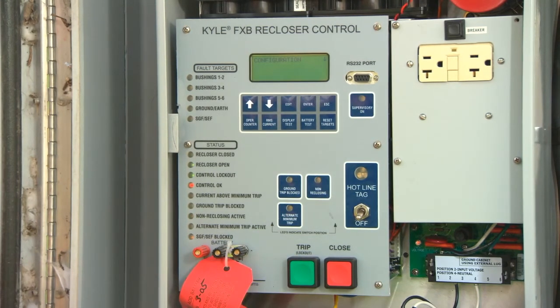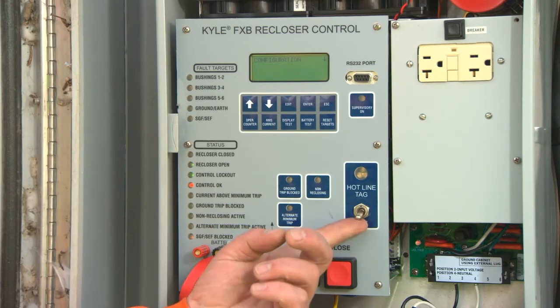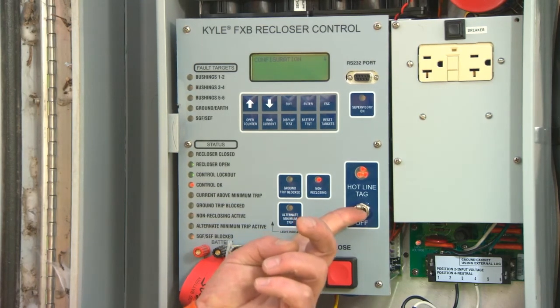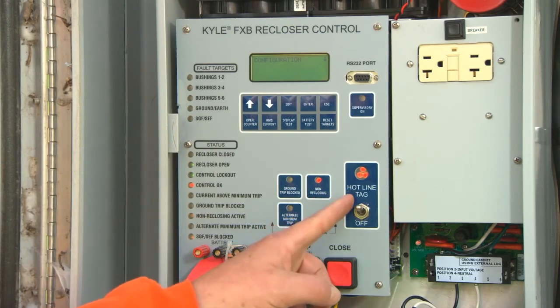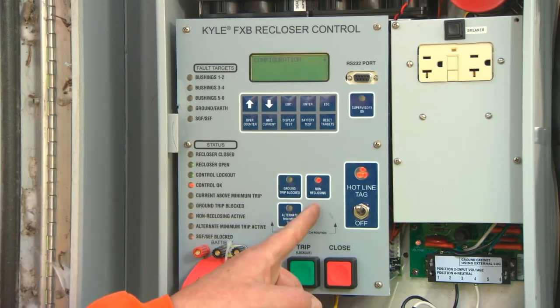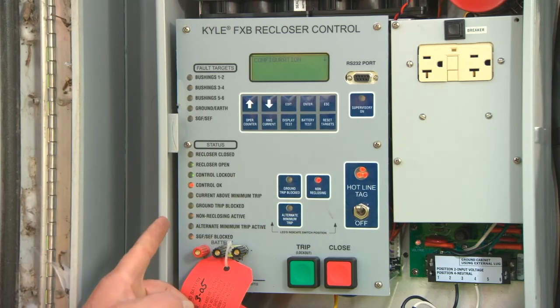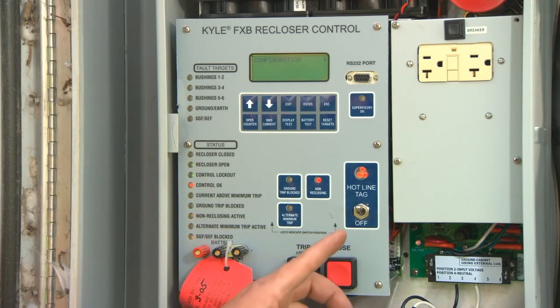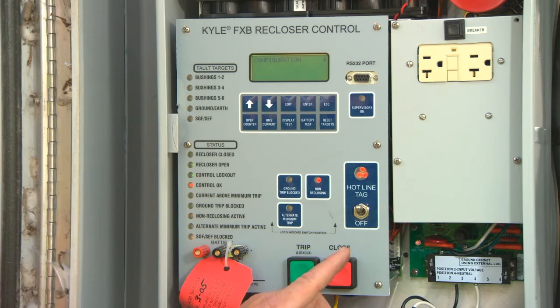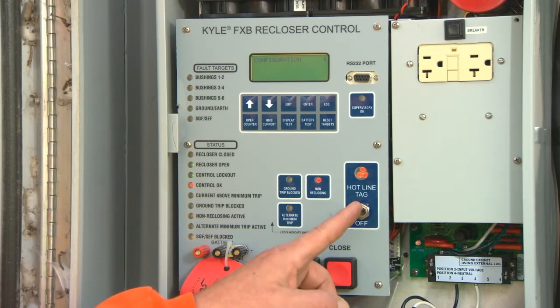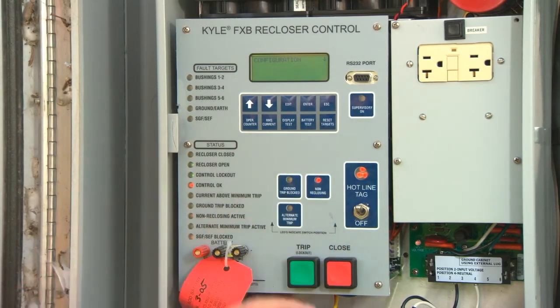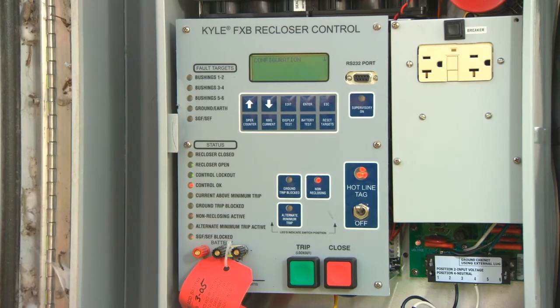The recommended way of applying a hotline tag is by switching the hotline tag switch on. You will notice the hotline tag LED, the non-reclosing LED, and the non-reclosing active LED all become illuminated. Throwing this switch eliminates any possibility of this control being activated by means other than this switch. If the supervisory LED was on, and this was connected to a SCADA system or a remote, an override would not be possible. The hotline tag must be installed or removed by personnel in the field.